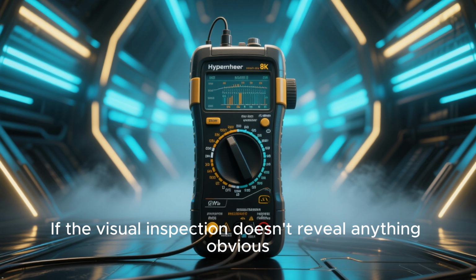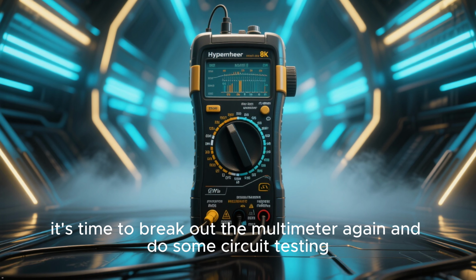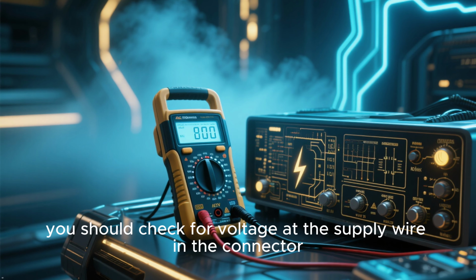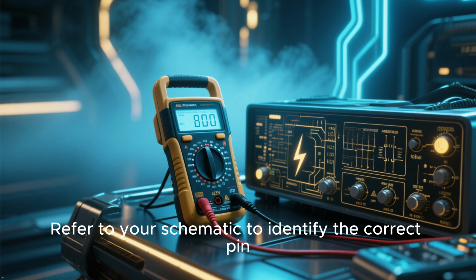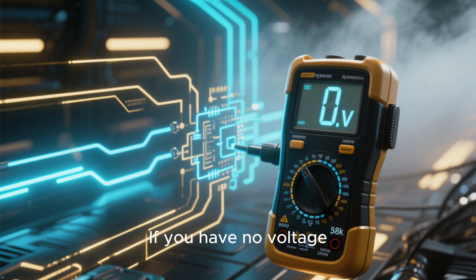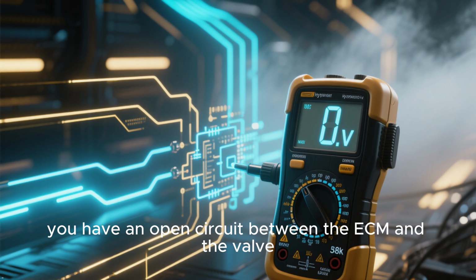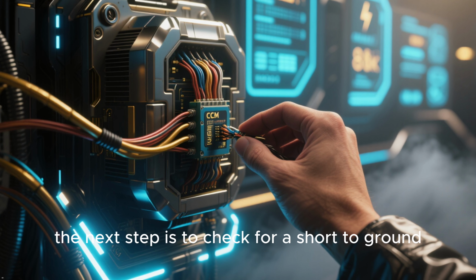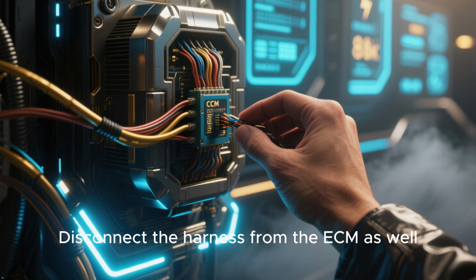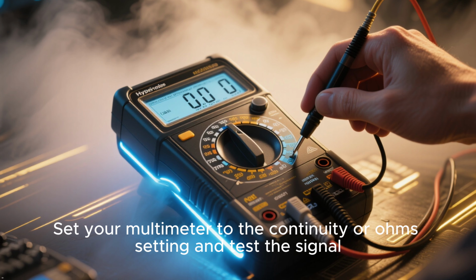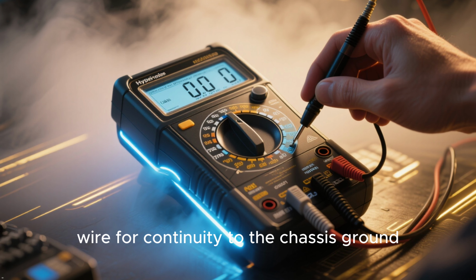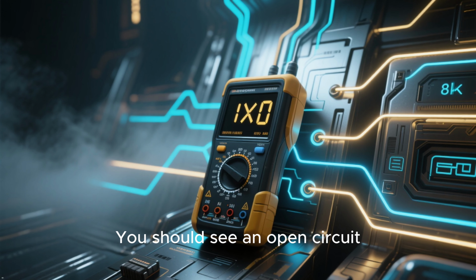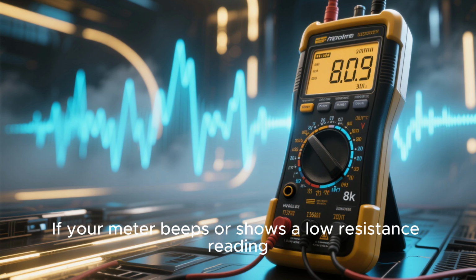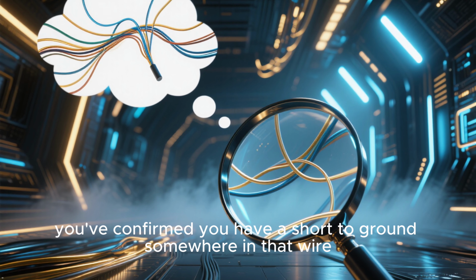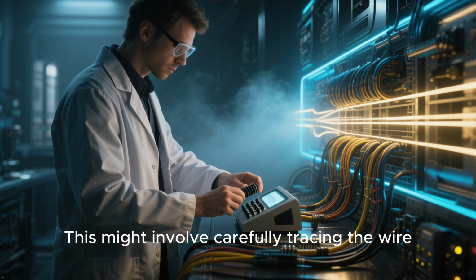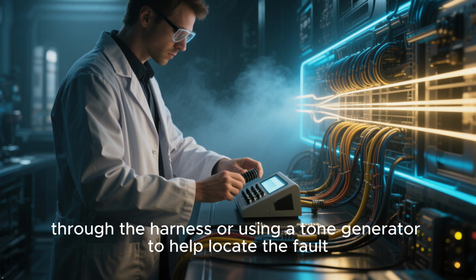If the visual inspection doesn't reveal anything obvious, it's time to break out the multimeter again and do some circuit testing. With the key on and the valve unplugged, you should check for voltage at the supply wire in the connector. Refer to your schematic to identify the correct pin. If you have no voltage, you have an open circuit between the ECM and the valve. If you do have voltage, the next step is to check for a short to ground. Disconnect the harness from the ECM as well, so the circuit is isolated. Set your multimeter to the continuity or ohm setting and test the signal wire for continuity to the chassis ground. You should see an open circuit or infinite resistance. If your meter beeps or shows a low resistance reading, you've confirmed you have a short to ground somewhere in that wire. Now you just have to find it. This might involve carefully tracing the wire through the harness or using a tone generator to help locate the fault.